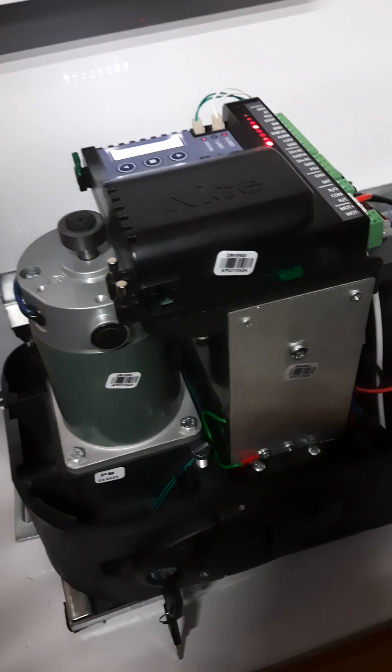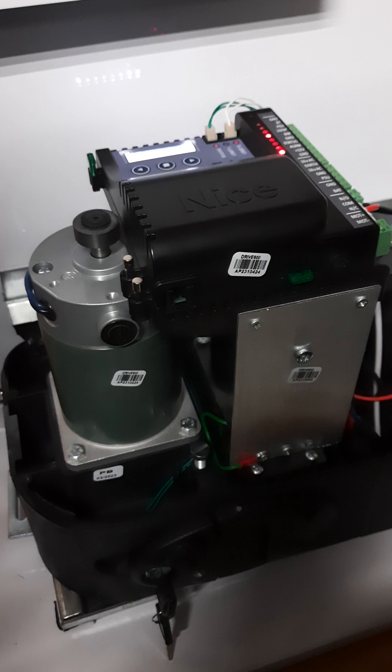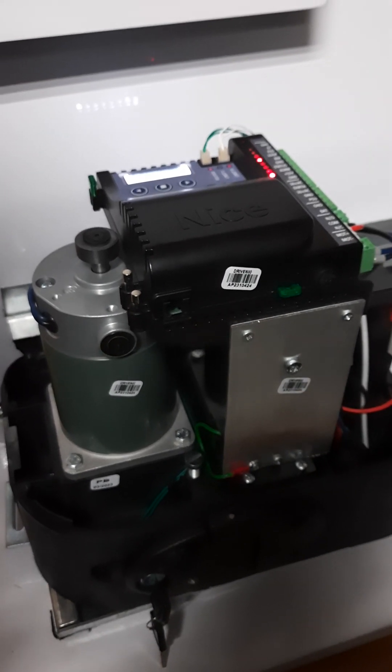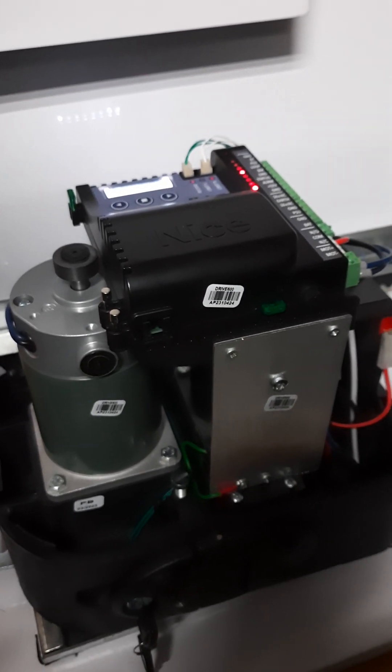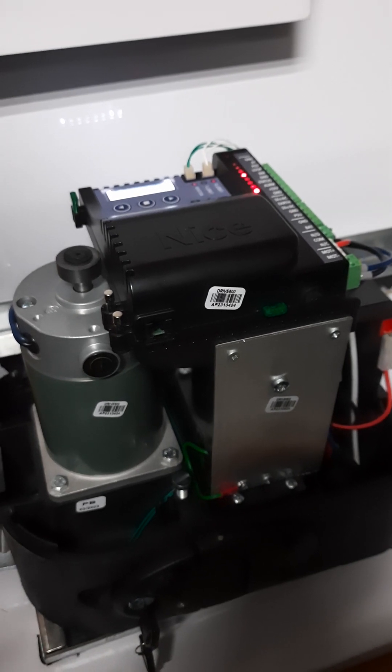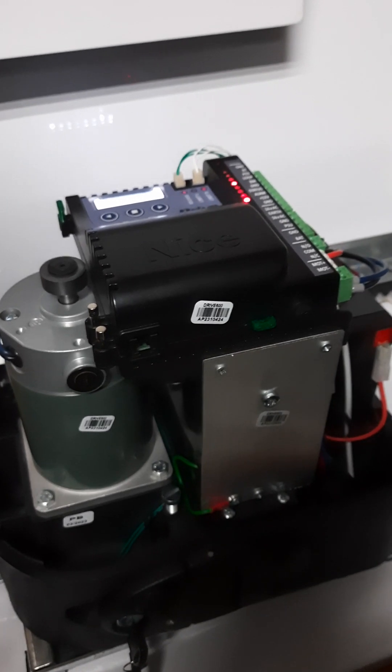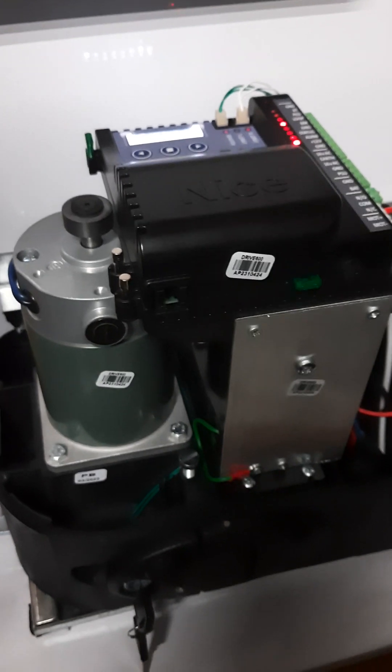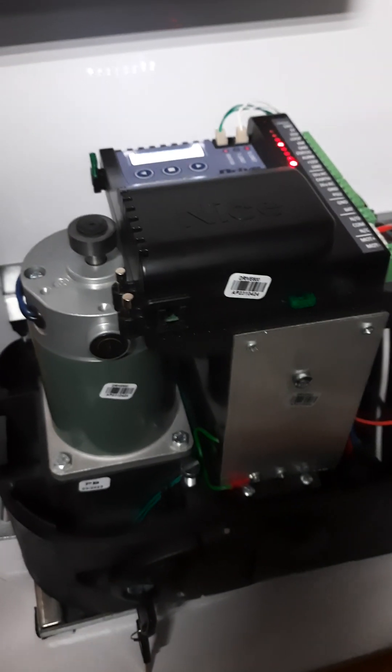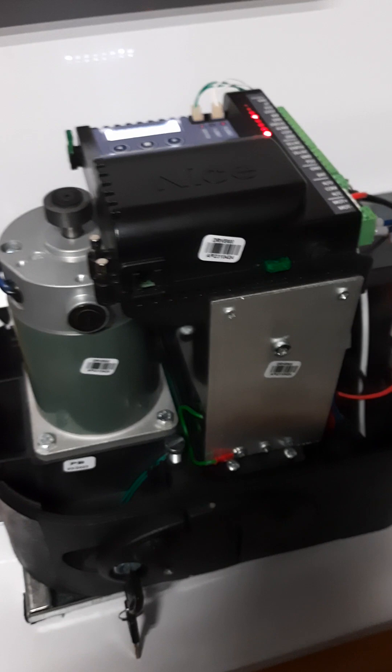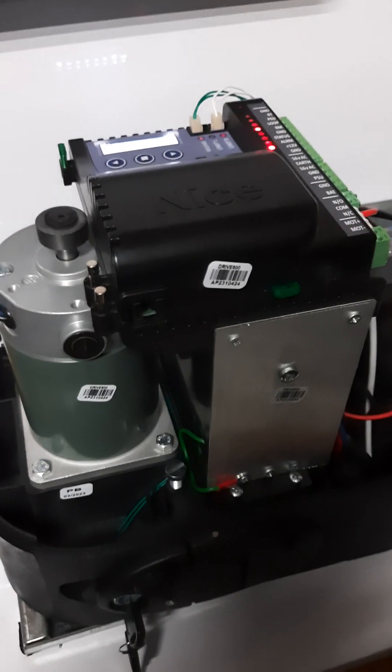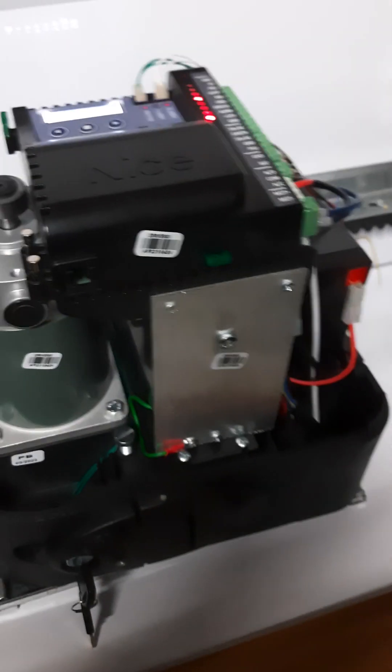Also just something to remember when installing beams. Sometimes with the sun in the morning and the afternoon, it is shining directly into the receiver. Sometimes it can interfere with that infrared beam. Then we just need to put some kind of like a little roof or a cover, just to protect the beam from the sun shining in there. We normally see it in the morning and in the afternoon, a specific time when the sun is shining. But not all installations are the same.